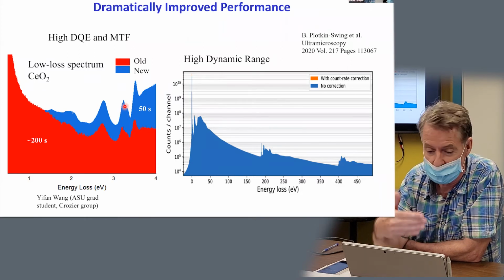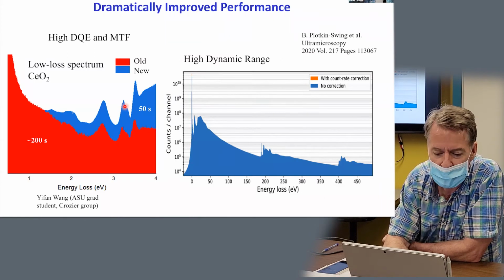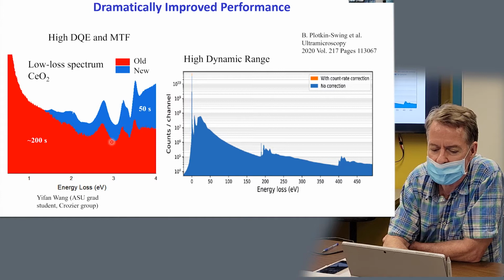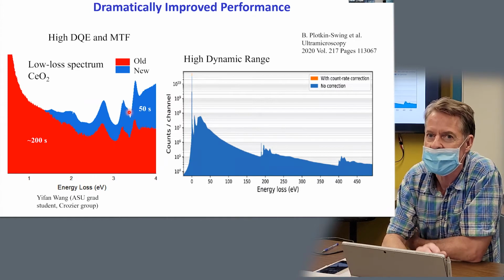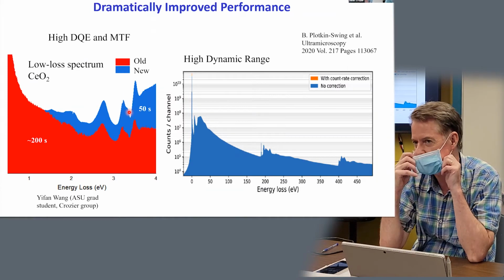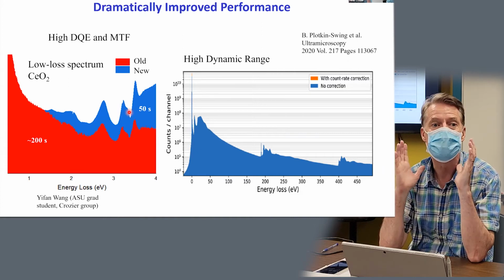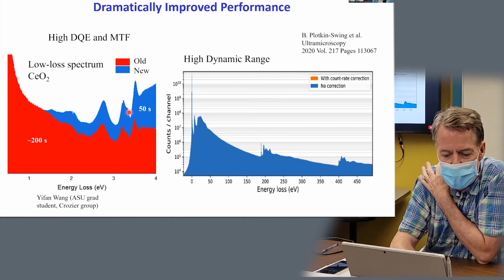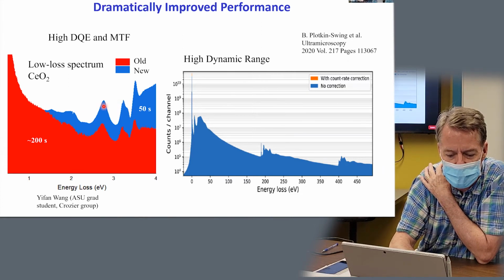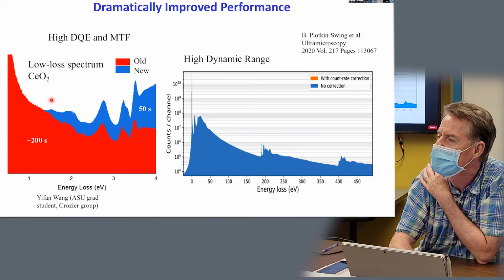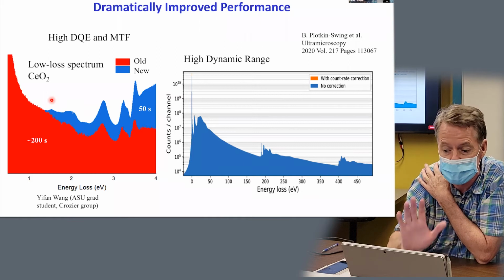So that's telling us that we're getting much more sensitivity. But the other thing I want you to notice is that the peaks are much sharper than the red curve. It's exactly the same area of the sample. The peaks are much sharper because the point spread function of this detector is much better. So you get much better quality spectra. And you might say, well, here it doesn't make much difference. But if you look at this part of the spectrum, we're really starting to see things now that we couldn't see before. So this is what's great.